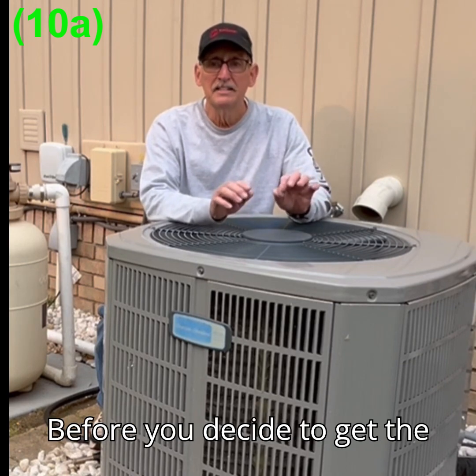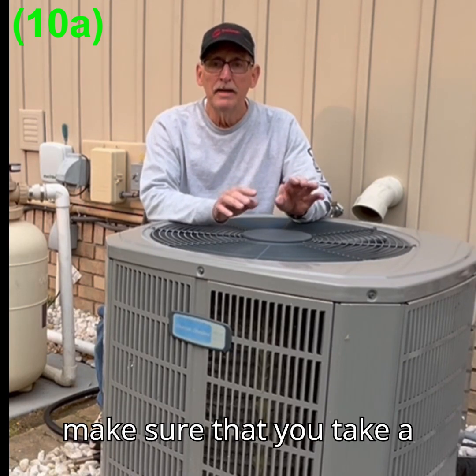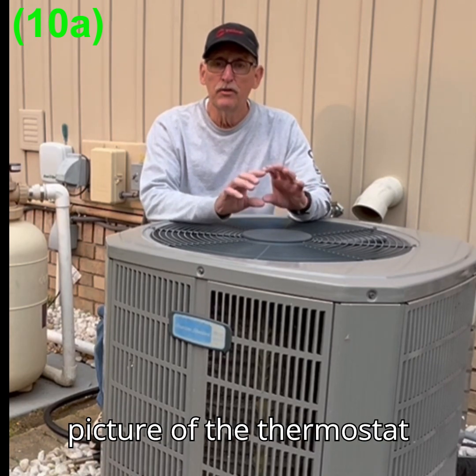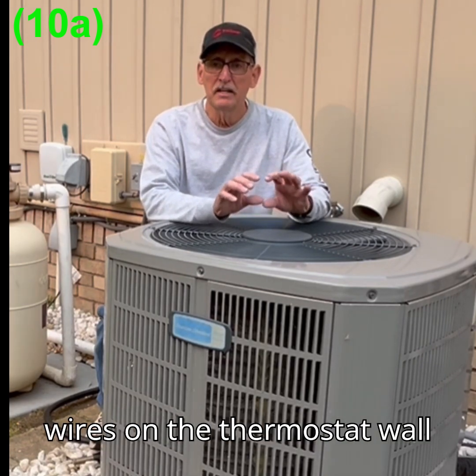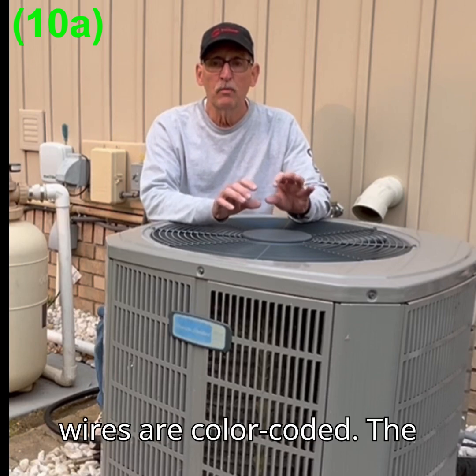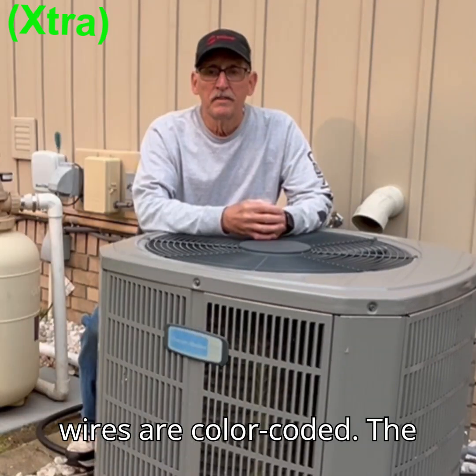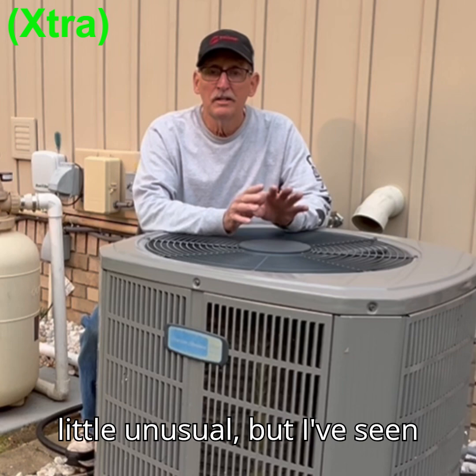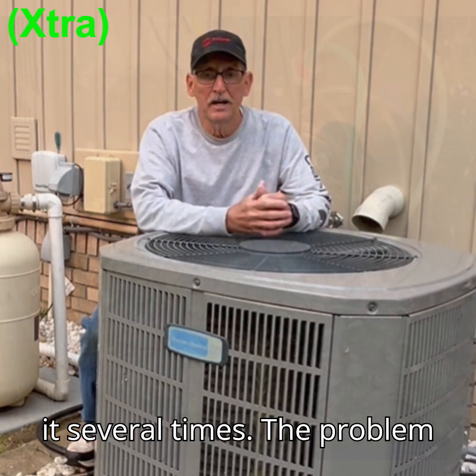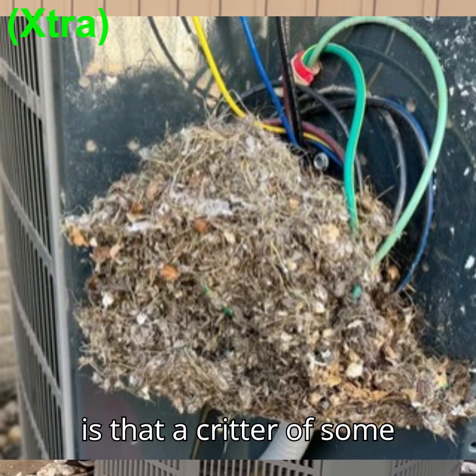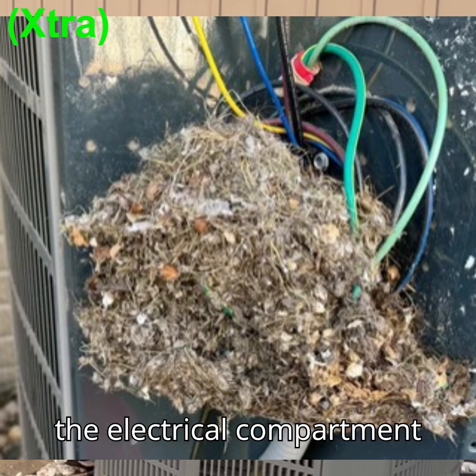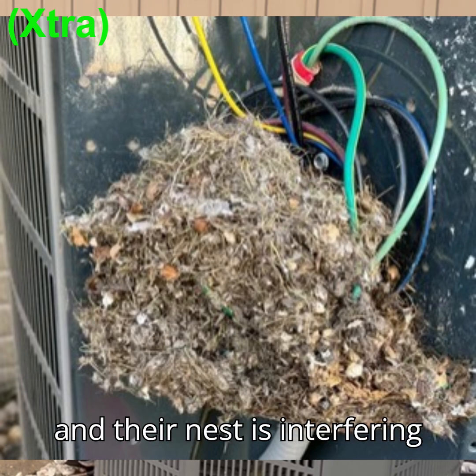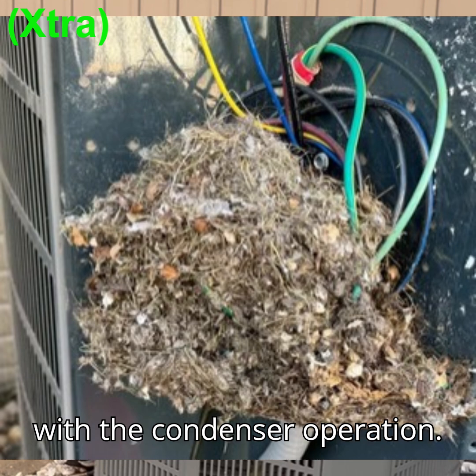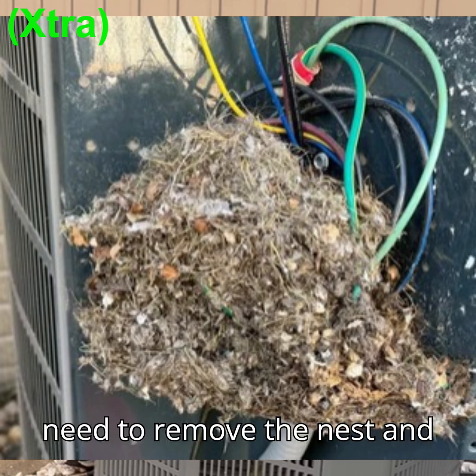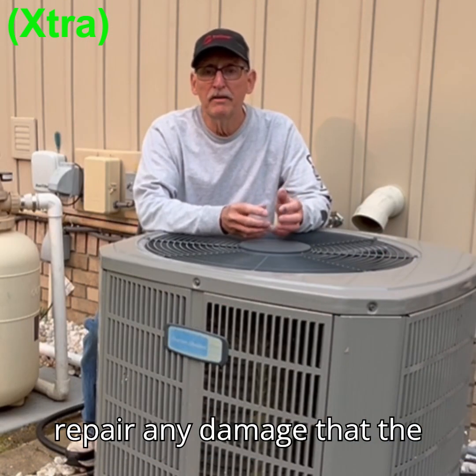Before you decide to get the new thermostat and change it, make sure that you take a picture of the thermostat wires on the thermostat wall plate. Usually, the thermostat wires are color-coded. The next problem might sound a little unusual, but I've seen it several times. The problem is that a critter of some sort has built their nest in the electrical compartment, and their nest is interfering with the condenser operation. So obviously, someone will need to remove the nest and repair any damage that the critter has caused.